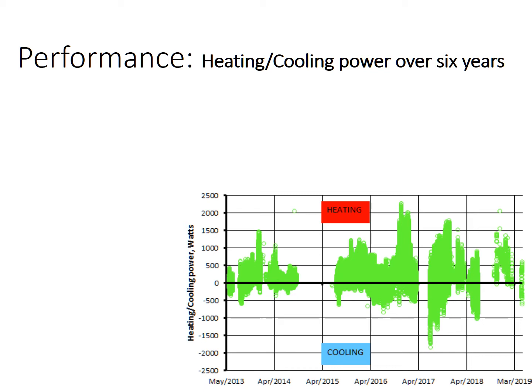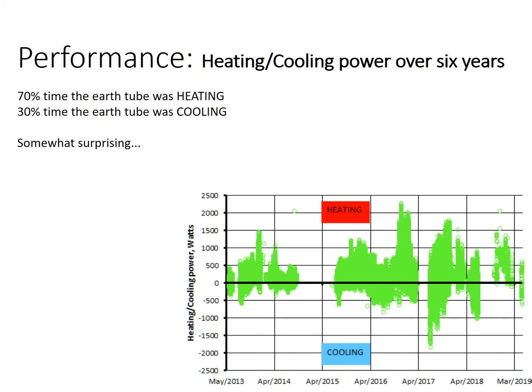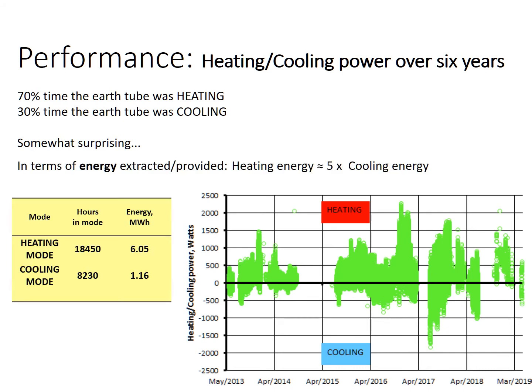Straight away one can see that there's more time spent in the heating mode than the cooling mode, and in fact it's 70% of the time the earth tube was heating, 30% cooling. This did surprise me. I thought earth tubes were mostly for cooling, and the heating or preheating of air really wasn't very important, but I was wrong. And in terms of energy rather than power, we can see over 6 years we've got 6 megawatt hours of energy for heating and 1 megawatt hour for cooling. So a very big difference, about 5-to-1 ratio, or 6-to-1.